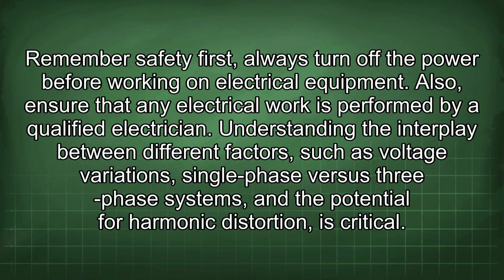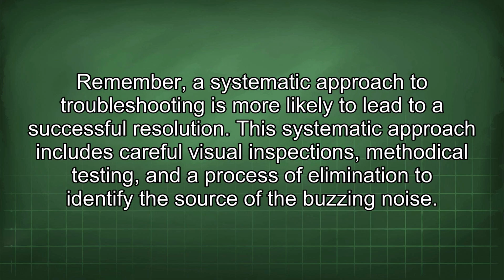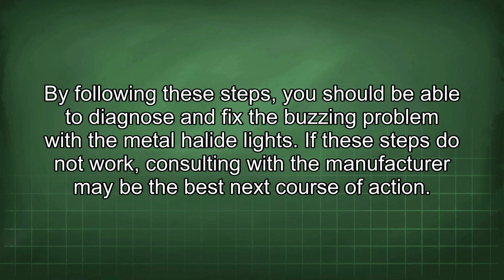Understanding the interplay between different factors such as voltage variations, single-phase versus three-phase systems, and the potential for harmonic distortion is critical. Remember, a systematic approach to troubleshooting is more likely to lead to a successful resolution. This systematic approach includes careful visual inspections, methodical testing, and a process of elimination to identify the source of the buzzing noise. By following these steps, you should be able to diagnose and fix the buzzing problem with the metal halide lights. If these steps do not work, consulting with the manufacturer may be the best next course of action.